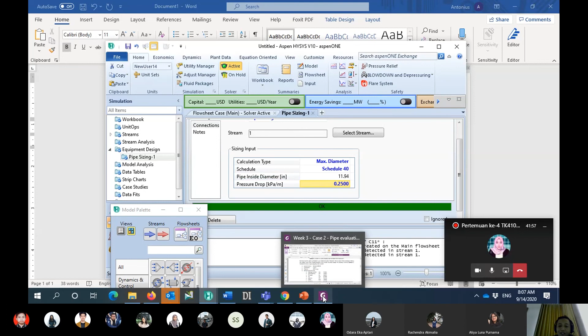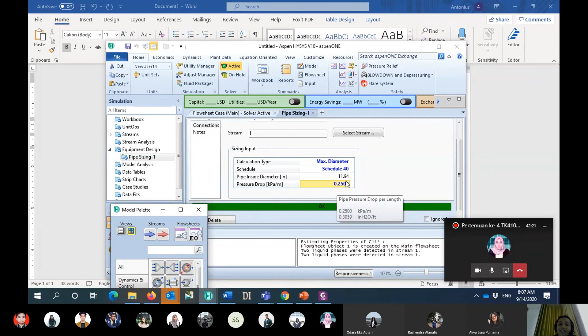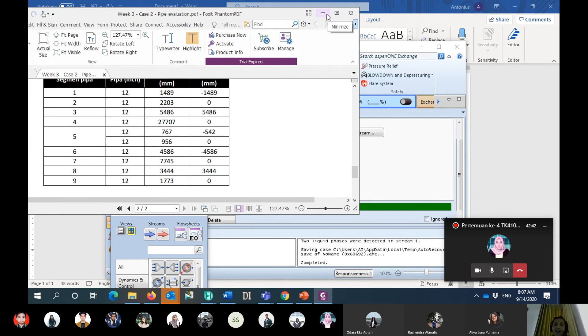So the designer of this plant is correct, because why? When I check with the pressure drop, defining the pressure drop following the criteria, the result of the pipe inside diameter is around 12 inch, which is the same as this one. Okay, so the first evaluation we have done, the pipe diameter is correct. It should be 12 inch.